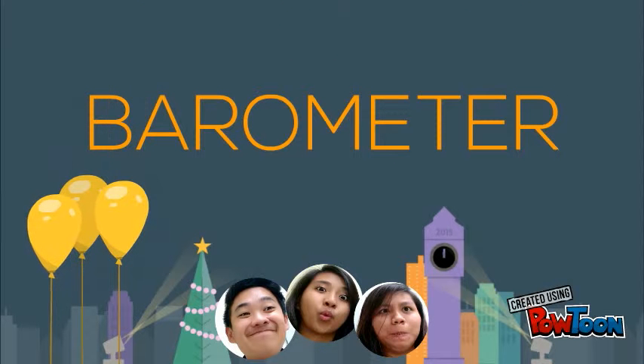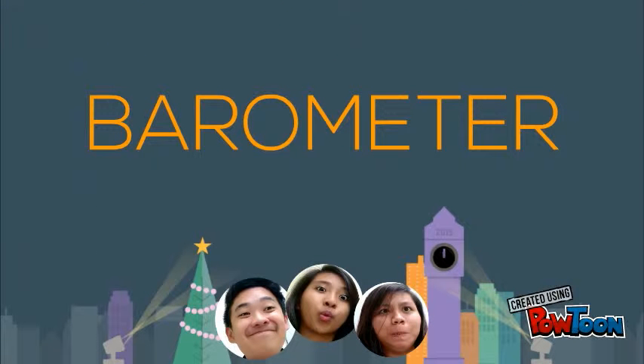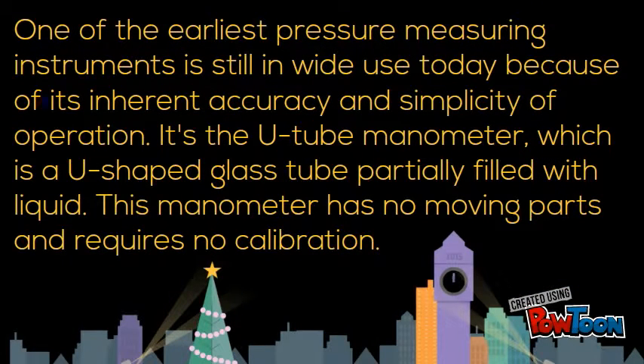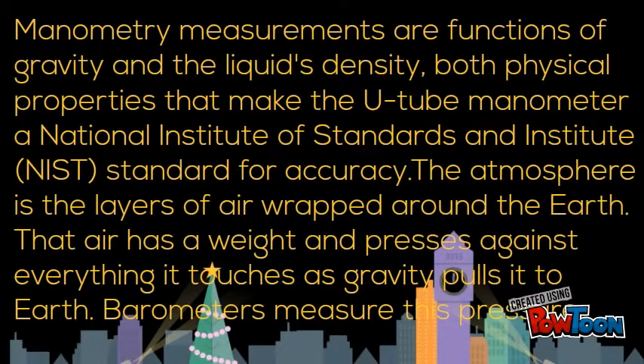One of the earliest pressure measuring instruments is still in wide use today because of its inherent accuracy and simplicity of operation — the U-tube manometer. It is a U-shaped glass tube partially filled with liquid, with no moving parts and no calibration required. Manometry measurements are functions of gravity and the liquid's density, both physical properties that make the U-tube manometer a NIST standard for accuracy.